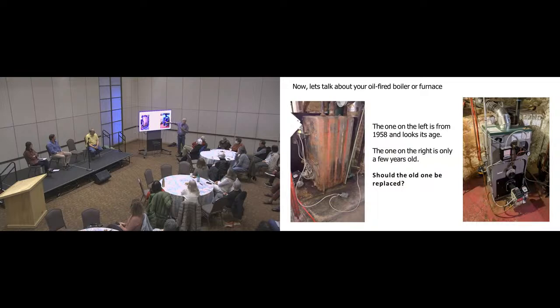I just want to talk about oil-fired heating equipment. This boiler over here is from about 1958, and it looks its age. This is a much newer boiler—this happens to be a steam boiler, and that's a hot water boiler. So how many people think we should get rid of that old one and put a new one in? Fair amount. That's understandable.